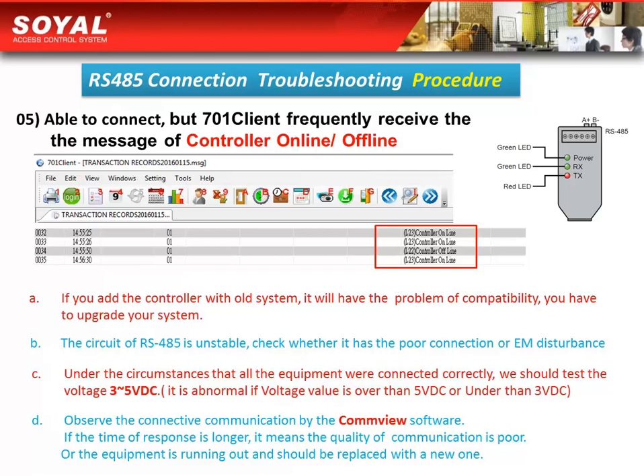Fifth, when the RS485 is able to connect but the 701 client frequently receives messages of 'controller online' or 'controller offline' — it sometimes shows online, sometimes shows offline — there are four possible reasons. First, if you added the controller with an old system, the system may be too old and have compatibility problems, so you have to upgrade your system.